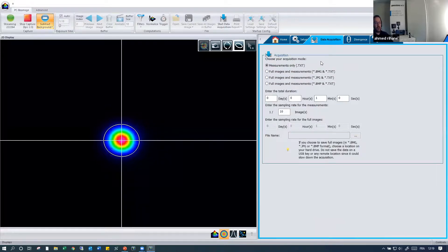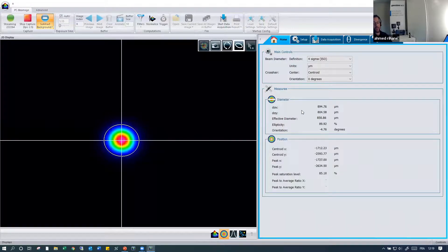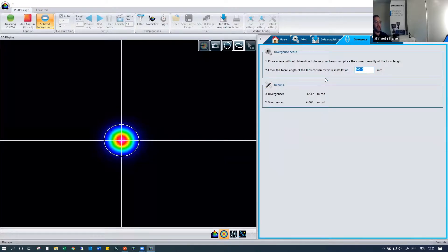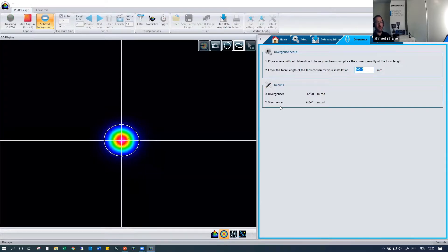You can also set up automatic acquisition mode with different formats — text or image — and enter the total duration of the acquisition. For outputs, you have the diameter in X and Y, ellipticity, rotation of the beam, centroid in X and Y, and peak position in X and Y. You can also get the beam divergence as an output: by using a lens with a known focal length — for example 200 mm — placing the camera at that focal length gives an estimation of divergence in X and Y. For more precise divergence measurement, our Beam M² system is available, but this gives a good approximation.